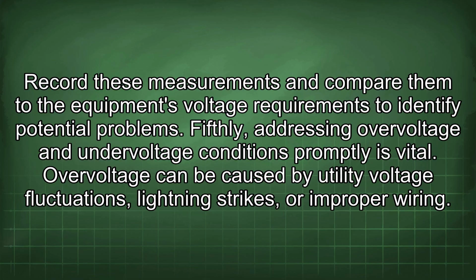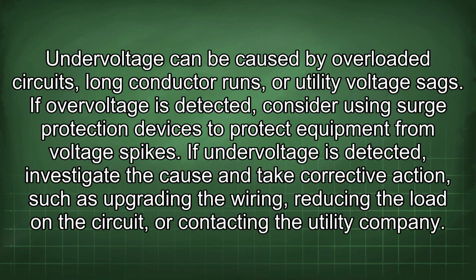Fifthly, addressing overvoltage and undervoltage conditions promptly is vital. Overvoltage can be caused by utility voltage fluctuations, lightning strikes, or improper wiring. Undervoltage can be caused by overloaded circuits, long conductor runs, or utility voltage sags. If overvoltage is detected, consider using surge protection devices to protect equipment from voltage spikes. If undervoltage is detected, investigate the cause and take corrective action, such as upgrading the wiring, reducing the load on the circuit, or contacting the utility company.